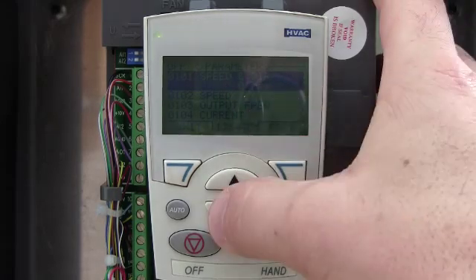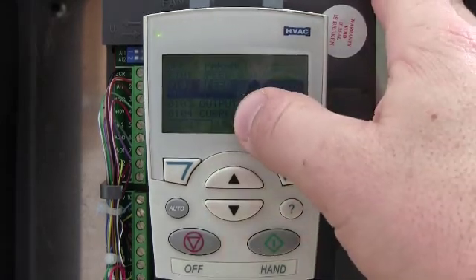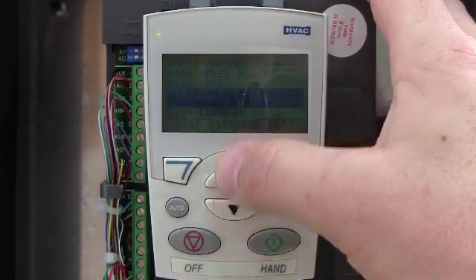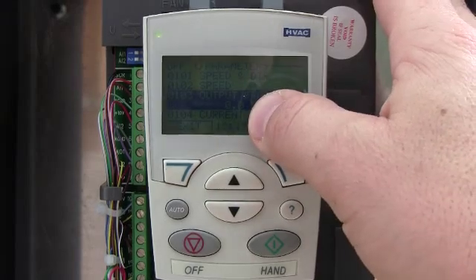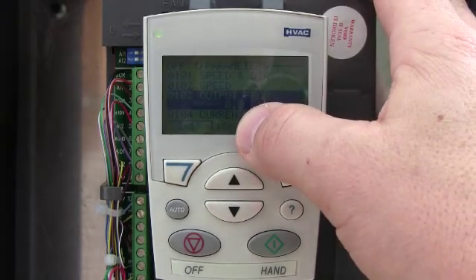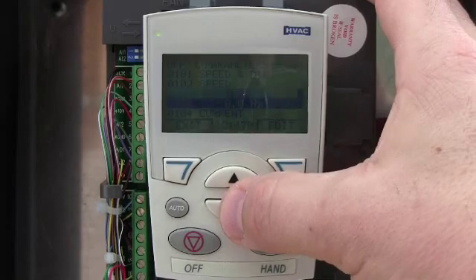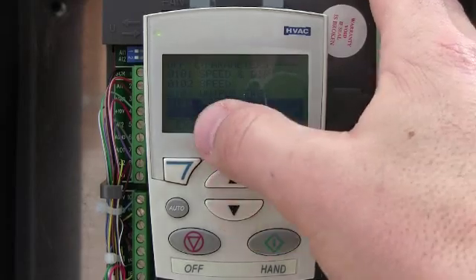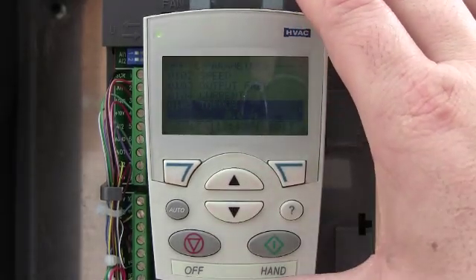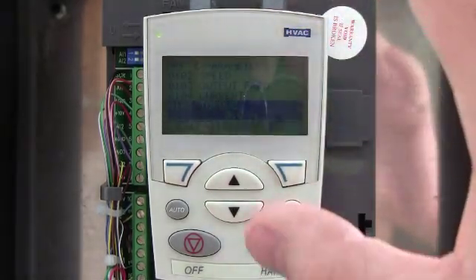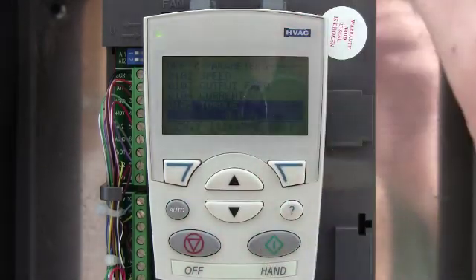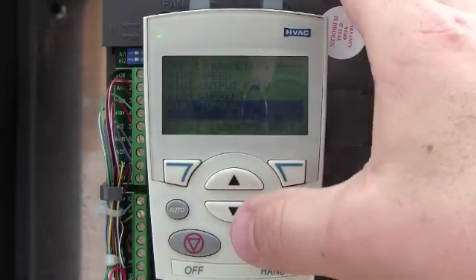The first one is RPM. The second one is your percent rated speed in RPM. Most of these are programmable, but this is your factory default. 103 is your output frequency, output current. So these are pretty much, generically speaking, what the drive is doing and also what the motor is pulling from it.